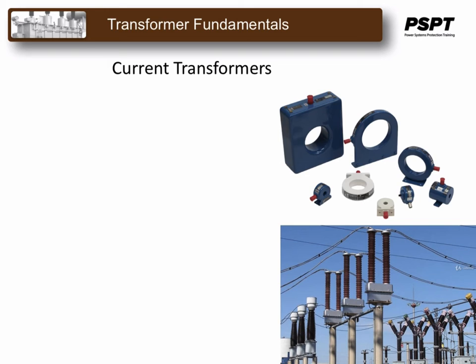This is why the secondaries of a CT should be shorted rather than opened when not in use, and should never be opened during testing procedures. Both the primary and the secondaries of CTs have relatively few turns of heavy wire and thus low impedance. Subsequently, a current is readily induced into the secondary proportional to the primary current. As we have seen, CTs behave according to this mathematical relationship, where the secondary current is given by the primary current times the turns ratio of the CT.